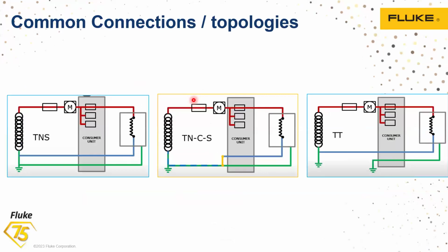So these are the common connections we actually see in industries. There are TN-S systems, then TN-C-S systems, and then TT systems. Now in a TN-S system, from the load, it is directly connected to the main point of the grounding. So the grounding and the neutral will be connected to the main point. This will be a TN-S system. And in the TN-C-S system, near the consumer unit, the neutral will be grounded to the actual grounding. And in the TT system, they will have separate grounding systems. So there are different types of connections or topologies which are commonly used.